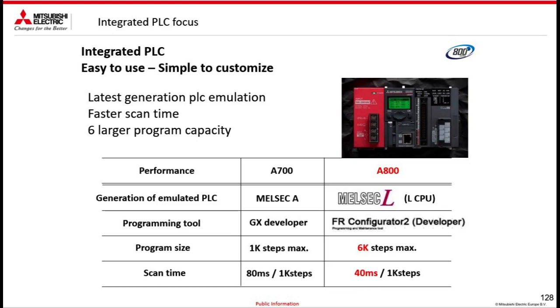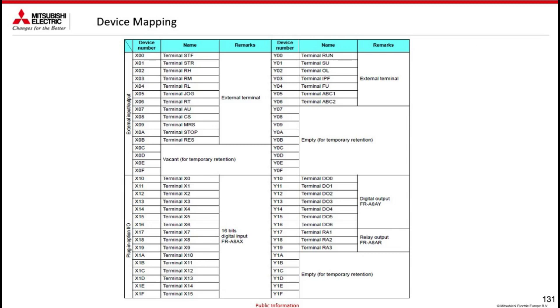As I was saying, the FR-F800, the FR-A800, and the FR-E800 inverters already bring an integrated PLC as standard, programmable in a classic way with the classic programming languages. For those of you who have already had experience with our PLC, it seems to mainly use GX Works 2. We manage the inputs and outputs as if it were a classic PLC. You see the inputs STF X0, STR X1, and so on.